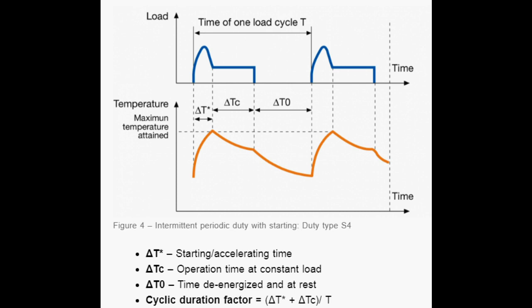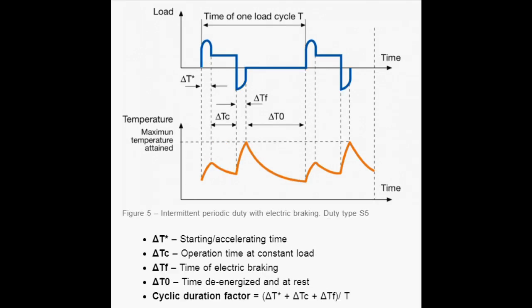S4 is identical to S3 but the starting time here is significant. The S5 is similar to S4, the only difference is the time of electric braking is significant here. So here in the sequence, we have a starting time, a time of operation at constant load, time of electric braking, and a time de-energized and at rest.